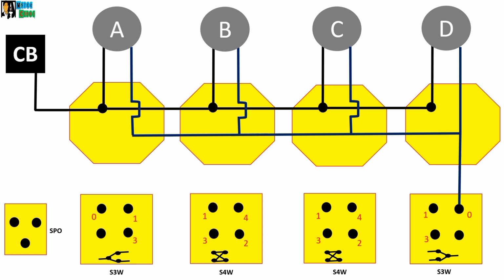Next, the traveler terminals of the 3-way switch: the one is connected to terminal 4 of the 4-way switch. The other traveler terminal of the 3-way switch, number 3, is connected to traveler terminal 2 of the 4-way switch.